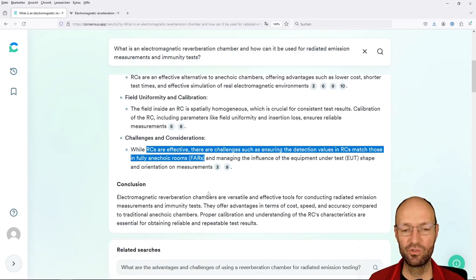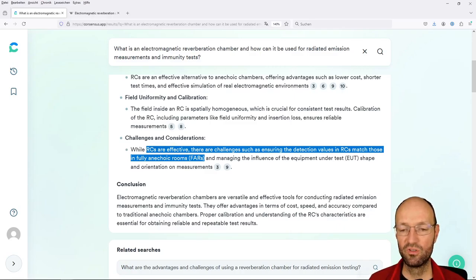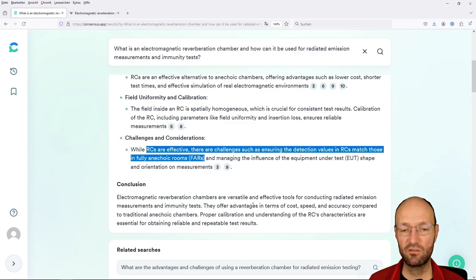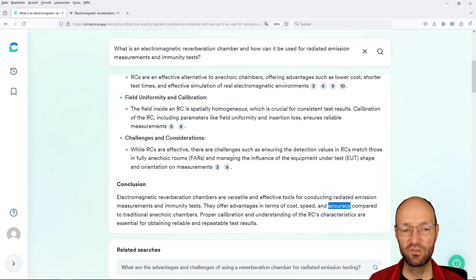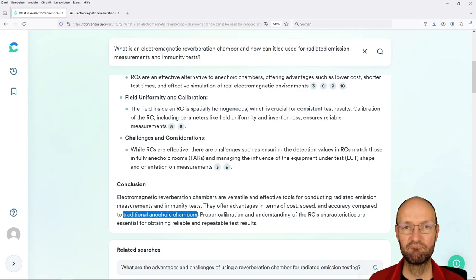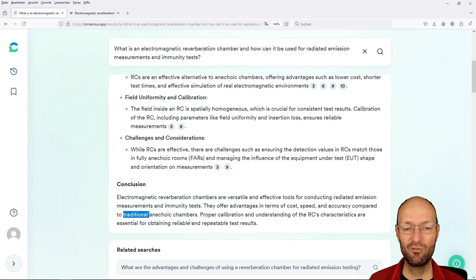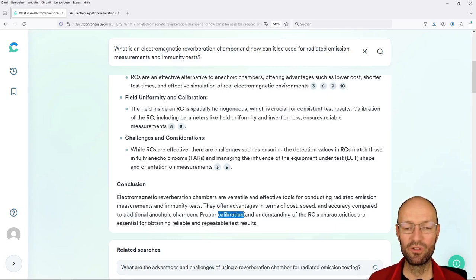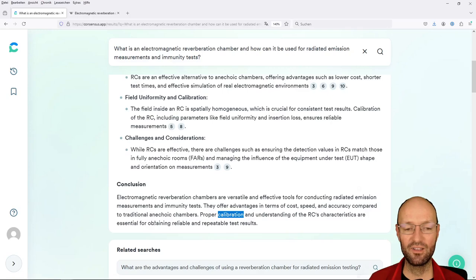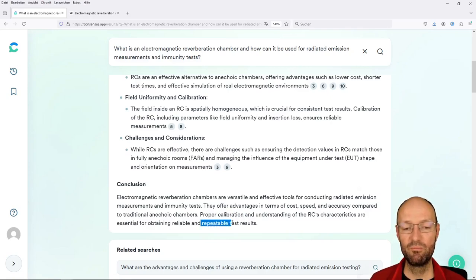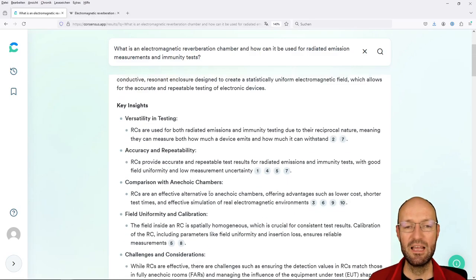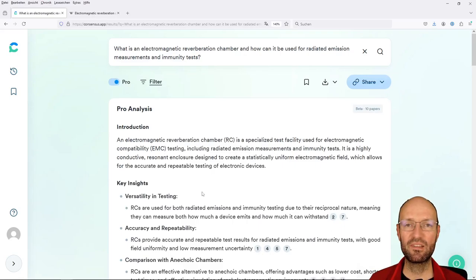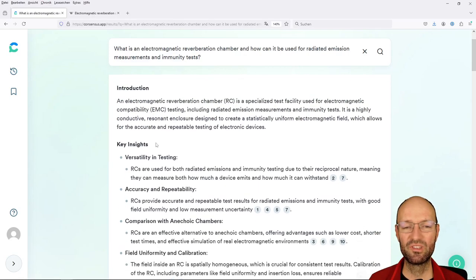There are limits given for this, but there are no limits given for the total radiated power here. So you need to do some conversion between the measurements of emitted field strength. And this is not super straightforward because you need to have the directivity of devices. There's some short conclusion: versatile, effective tools for conducting radiated emission measurements and immunity tests. And the advantages are cost, speed - I would doubt this - and accuracy. I would doubt this. Once again, I would doubt and question repeatable and would rather call it robust.